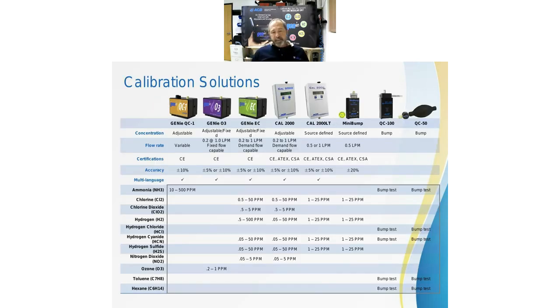So here you see some of the ranges. This is more specific on what outputs we can get with what gases we have. You see, for example, the GENie QC-1 unit is used for ammonia, so its range is anywhere between 10 and 500 parts per million. One of the unique things we also have that cylinder gases don't have is the ability to do parts per billion. And you can see the hydrogen cyanide and hydrogen sulfide units go down to 0.05 parts per million. So that's 50 parts per billion. So we can make very low, very accurate amounts of calibration gas. And again, these are not stored under pressure, but rather generated on demand when they're needed.